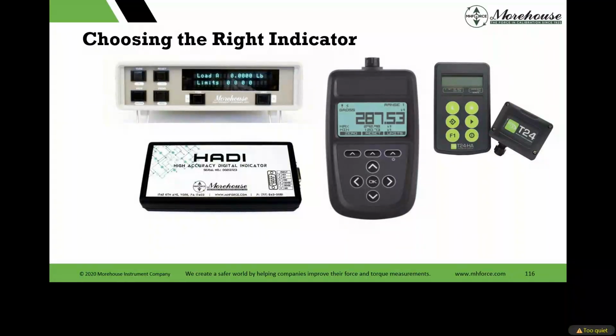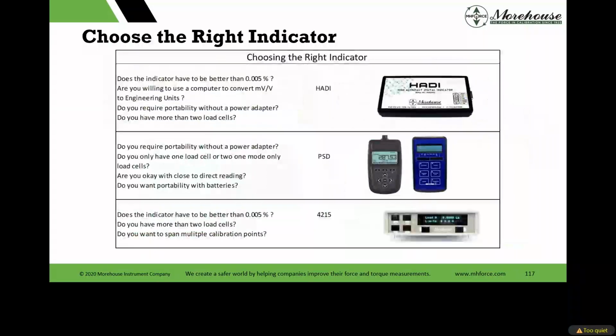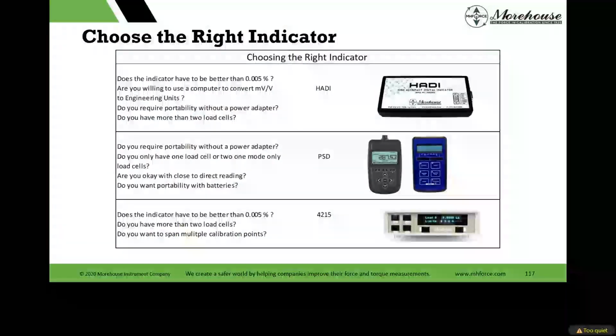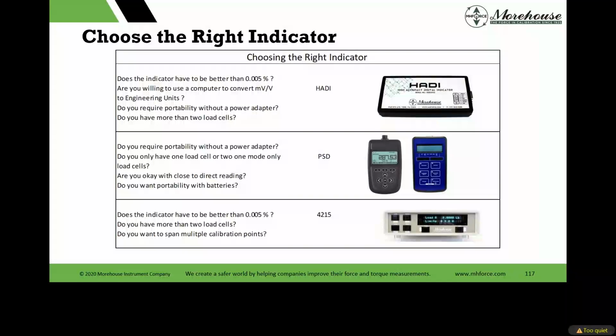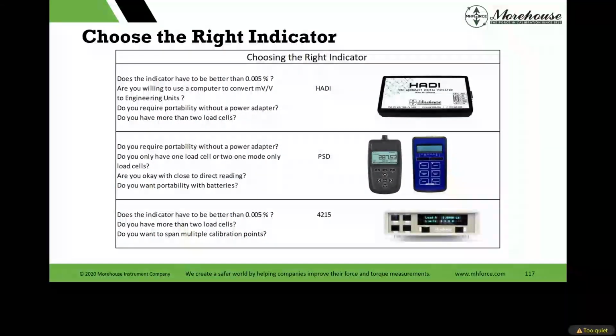So if you want a very, very good cell, it's going to be the Morehouse ultra precision shear web and one of these meters. And then you have to decide what you want meter wise. Can I live with a computer? Does the indicator have to be better than 0.005%? That's a nonlinearity specification. I don't care too much about nonlinearity specifications. To some extent, you need to decide how easy do I want to make things for myself and for my technicians? How close do I want to be to nominal values?